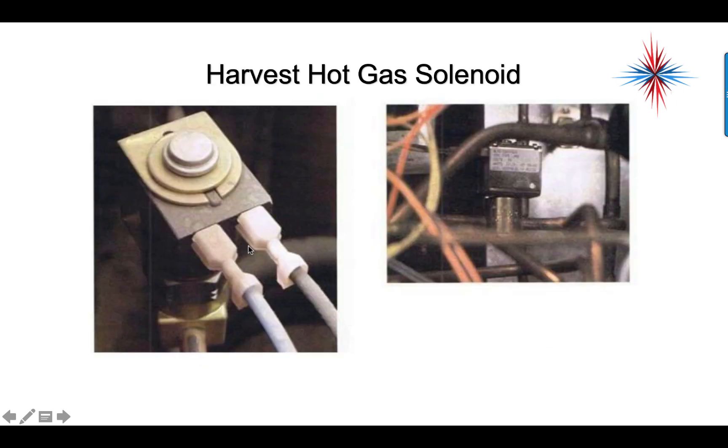Harvest gas hot gas solenoid is just like any other hot gas solenoid. Two power, L1 and neutral, or L1, L2 come into it. It's a mechanical electrical part. The top of this, which is the coil, can be replaced without recovering refrigerant - it's two separate parts. It's very rare for the mechanical side of this to fail. Nine out of ten times, it will be the electrical side of it that fails.